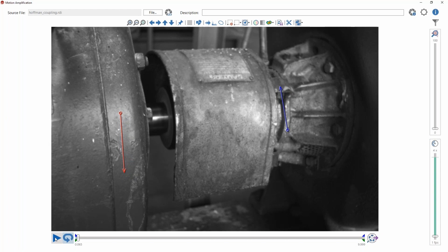And then the next, in sort of being intuitive, you can overlay 2 plots to show, the graph on a plot, one's going up while the other's going down. But for me, I think the most intuitive is just to show one arrow pointing one way and another arrow pointing another way, and even better to be able to show that over time. And so that really tells me very easily that one side is going up while the other is going down, so we're out of phase, and that's a problem.